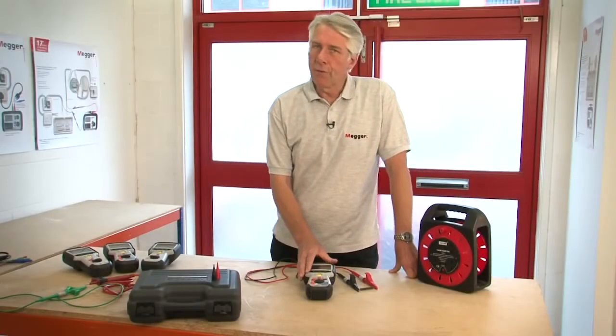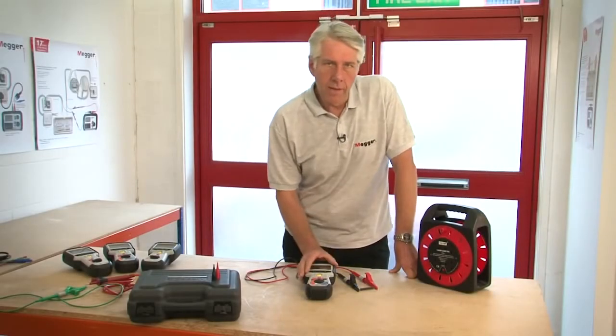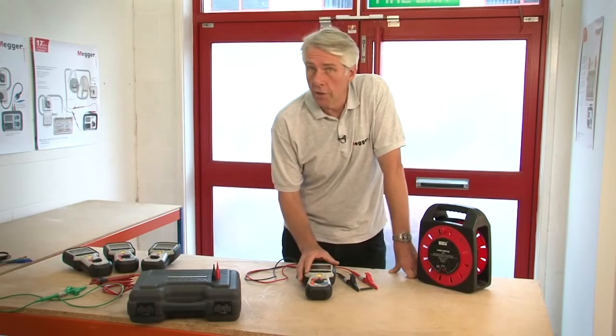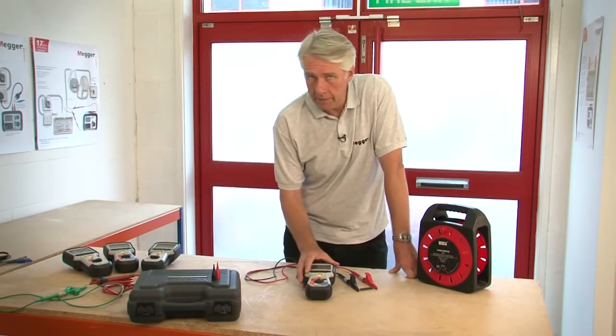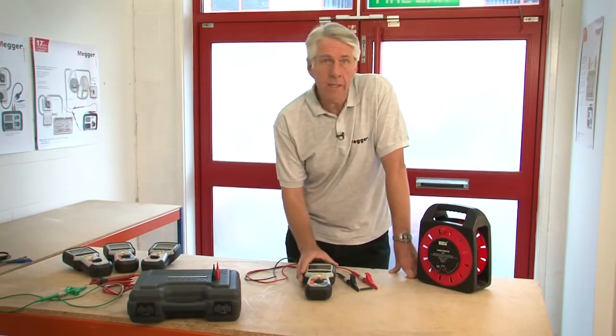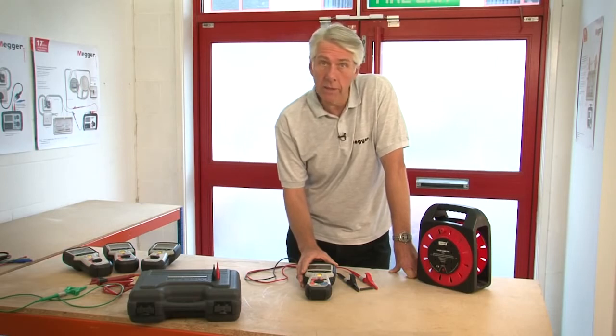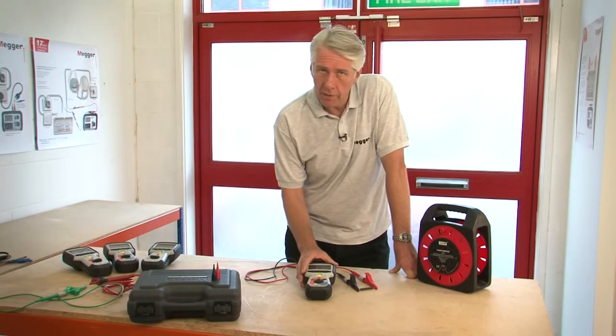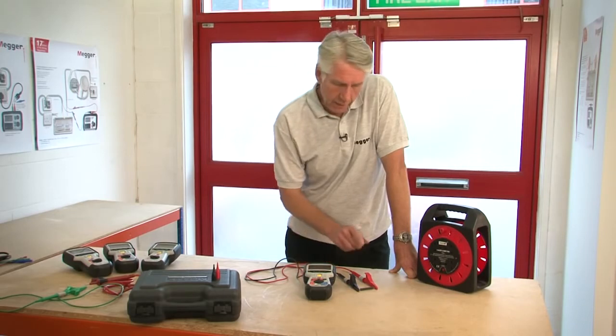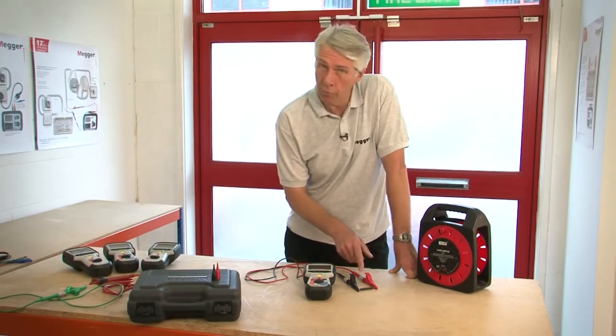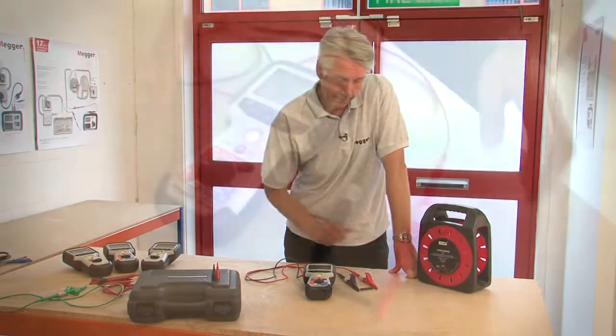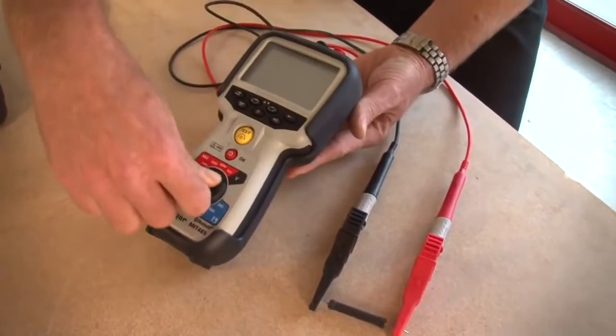Using an MIT400, what I'm going to do now is a demonstration of the insulation testing, continuity testing with a buzzer, and I'll also show you the test inhibit, which occurs if the product is inadvertently connected to a live supply. For the purpose of demonstrating the insulation test, I've connected a 25 megohm resistor between the red and black crocodile clips. So first of all, we select the test voltage.